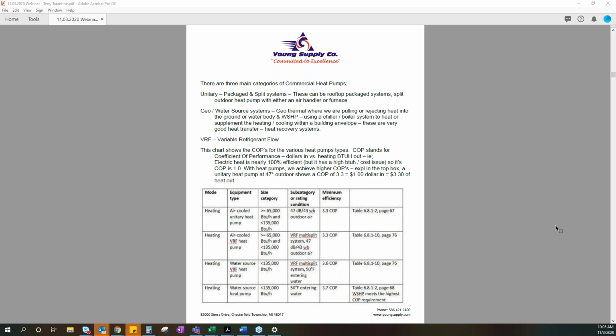When we talk about geo and water source systems, this is where we're pulling or rejecting heat from the ground or a water body or a water loop system, which many of you have in larger buildings. And what we're doing there is transferring heat amongst the building. We're using a chiller and a boiler, and we're starting to see some heat pump chillers come into the market as well to gain some efficiency. These are very good at heat transfer, and they lend themselves extremely well to heat recovery. And that's becoming the biggest focus of heat pumps these days, is we want to transfer heat amongst the building. We'll talk a lot more about that today.